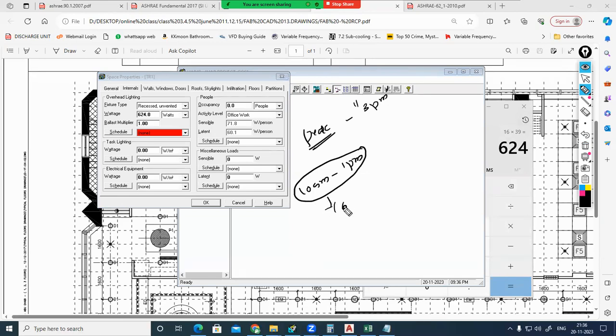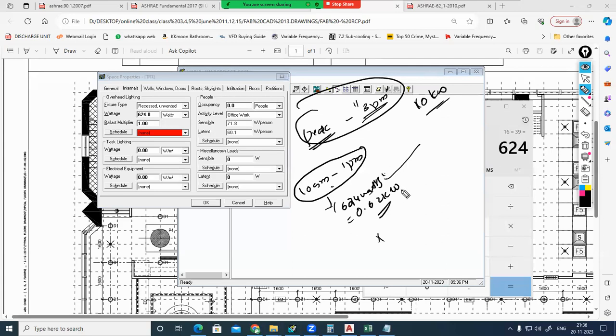How much is it? 624 watts of light fittings. All the other peak will come like 10 kilowatts, for example. Lighting load is 0.624 kilowatt, watt divided by 1000. But you can see the peak load is happening at 3 p.m. only. At 3 p.m., this office will be off. So that's why at 3 p.m., the software will not consider the 624 watts.